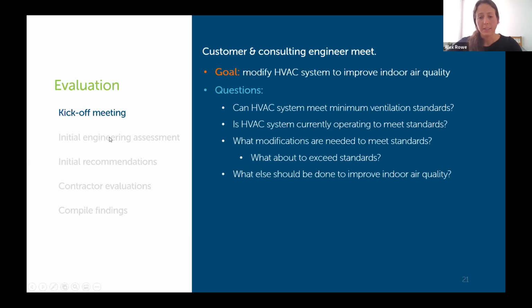They then asked their engineer to determine the following. Can their HVAC system meet the minimum standards for ventilation? Is it as designed? So is it capable of meeting those minimum ventilation standards per the mechanical design? Then, if it can, is the HVAC system currently operating to meet those standards? And if it's not, what modifications are needed to meet the standards? And then what about to exceed the standards? And then what else should be done to improve indoor air quality as it relates to the HVAC system?